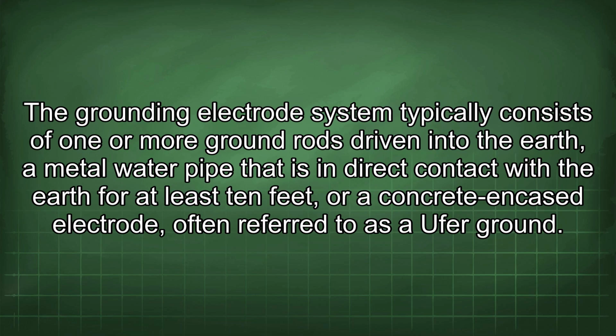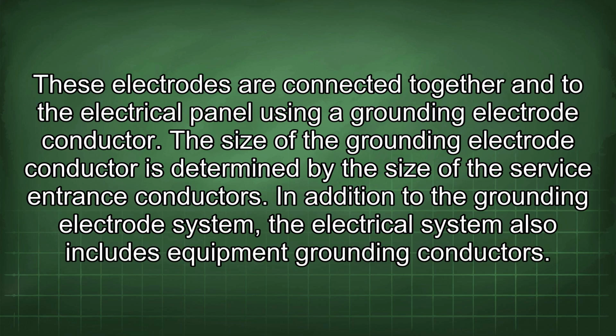The grounding electrode system typically consists of one or more ground rods driven into the earth, a metal water pipe that is in direct contact with the earth for at least 10 feet, or a concrete encased electrode, often referred to as a UFER ground. These electrodes are connected together and to the electrical panel using a grounding electrode conductor. The size of the grounding electrode conductor is determined by the size of the service entrance conductors.